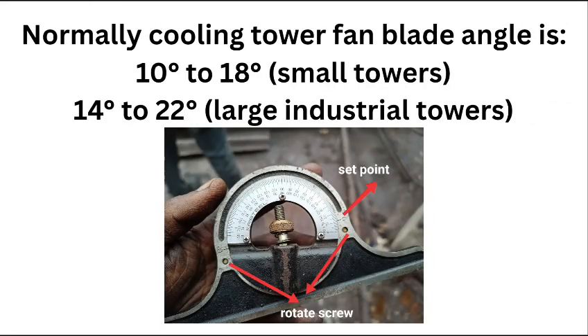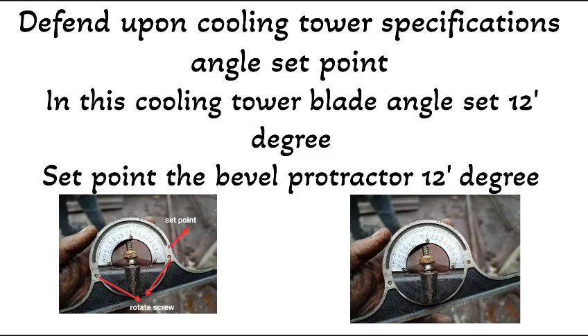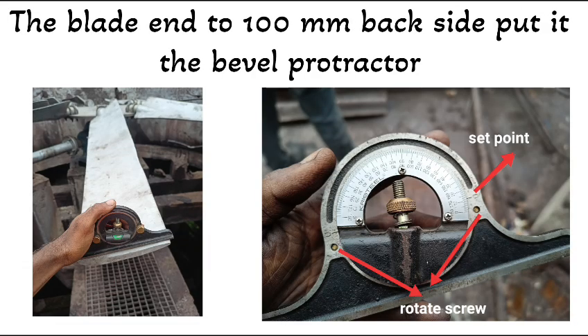Normally the cooling tower fan blade angle is 10° to 18° for a small cooling tower and 14° to 22° for a large industrial tower. It depends upon the cooling tower specifications and angle set point. In this cooling tower the blade angle is set to 12°. Set the bevel protractor to 12°. Put the bevel protractor 100 mm back from the blade end.